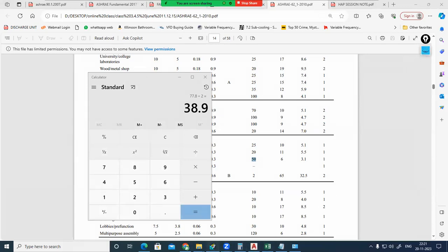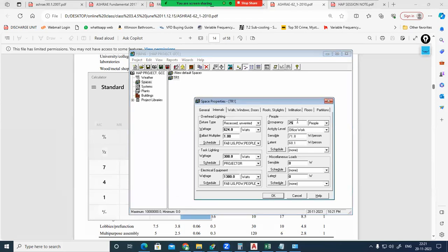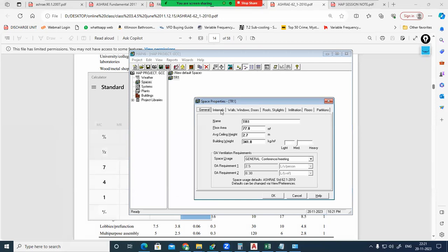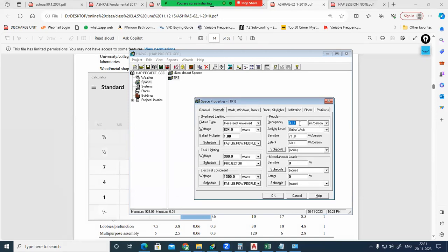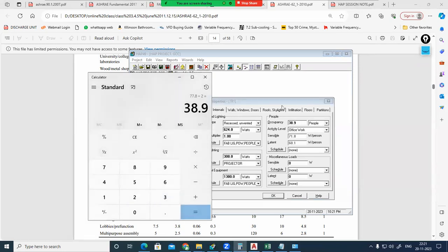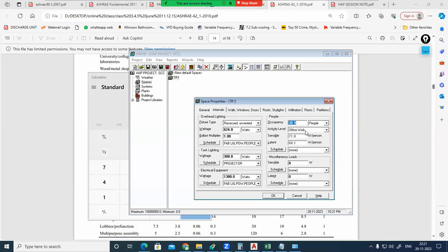39, correct. For example, we can come here. Instead of number of people, I'll be selecting meter square per person. You know, 77.8 meter square. So for meter square per person, I'll be providing 2 meter square, if it is a conference room. Now, if you want to find the number of people, after providing the meter square per person value of 2, you can change that into people. It will be 38.9 people. 38.9 people is not possible, so you can round that to 39.